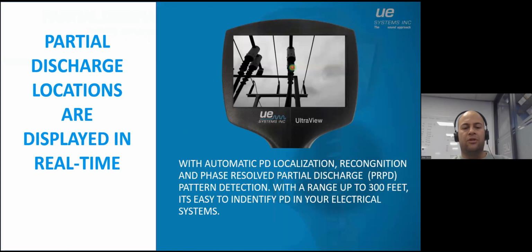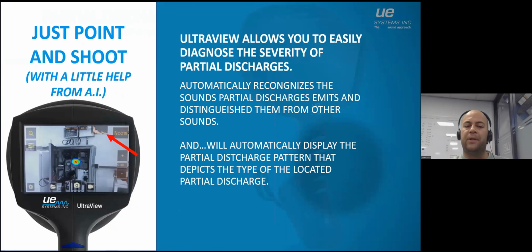Partial discharge locations are displayed in real time, with automatic PD localization, recognition, and phase-resolved partial discharge (PRPD). It recognizes what kind of problem it is, so you can find leaks and discharges from a very far distance. PRPD can tell if something is electrical related or not.